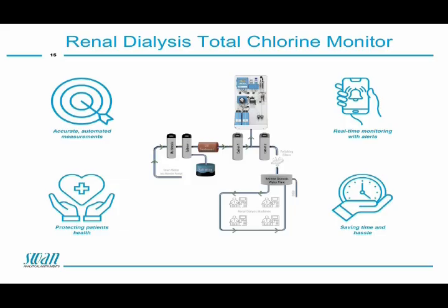What can we do about it? Like I said, SWAN can provide this continuous monitoring of total chlorine. It's an analyzer that sits between carbon 1 and 2 and logs every 10 minutes a total chlorine result. There is high accuracy because it's an analytical instrument. You've got your cloud-based data, clear insights and early warnings, so results can alarm on your portable phone, your PC, whatever you want. It provides graphs like this, so graphic evidence of what is happening.